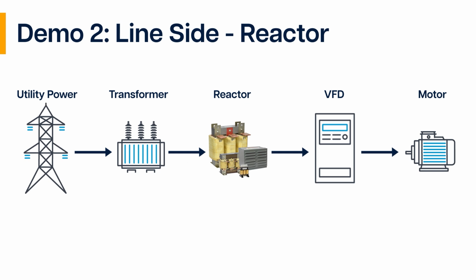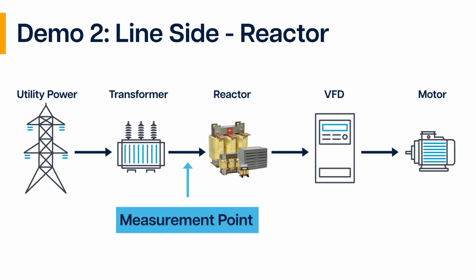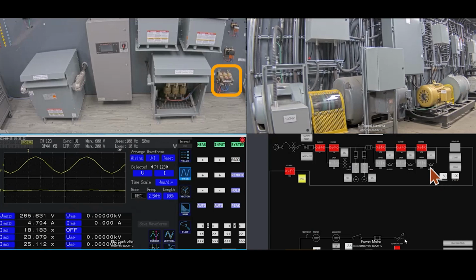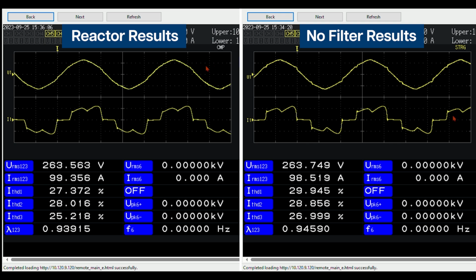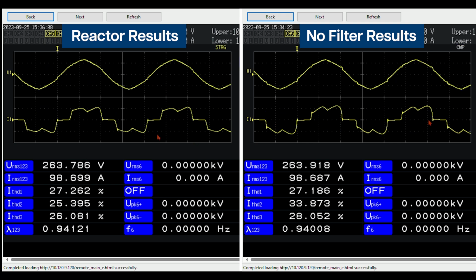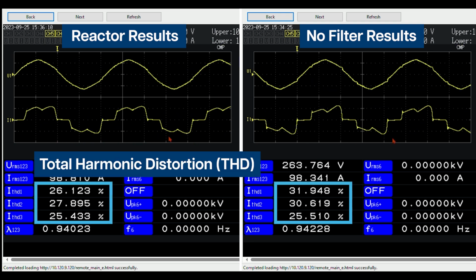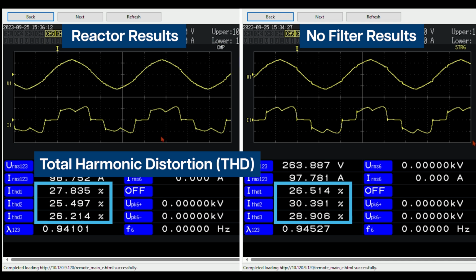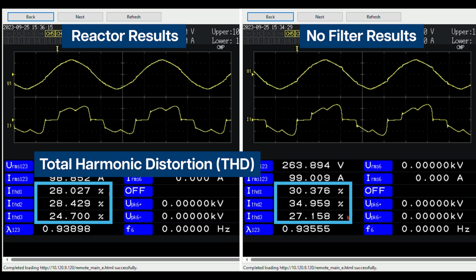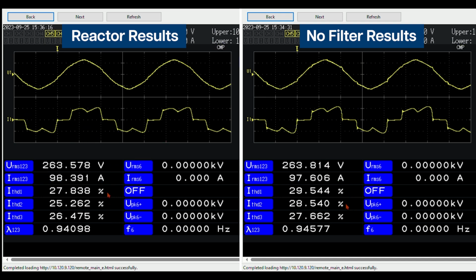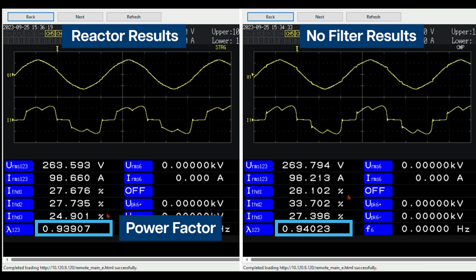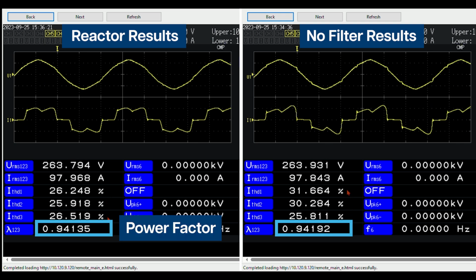For Demo 2, we will insert a line reactor into the circuit. A line reactor is typically recommended at the input of each drive, especially those without a DC link choke, to modestly reduce harmonics. A line reactor introduces impedance into the electrical circuit, helping to diminish harmonic distortion.